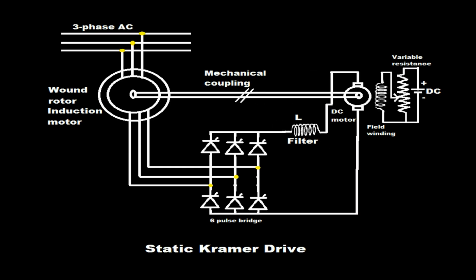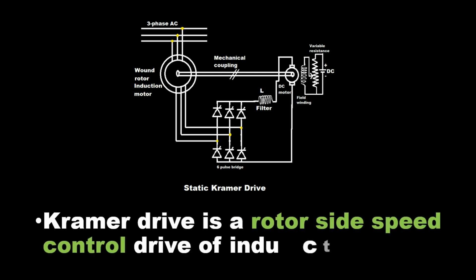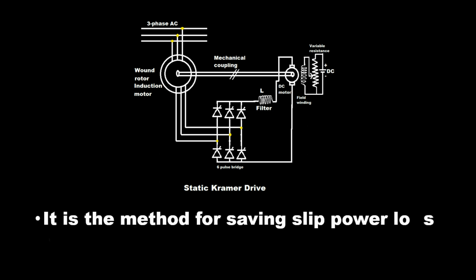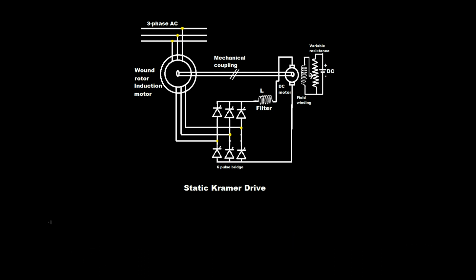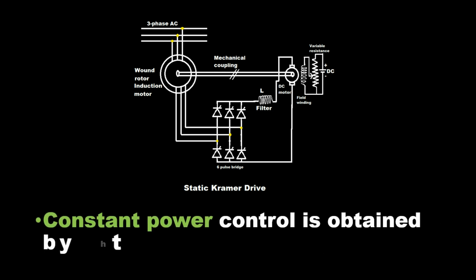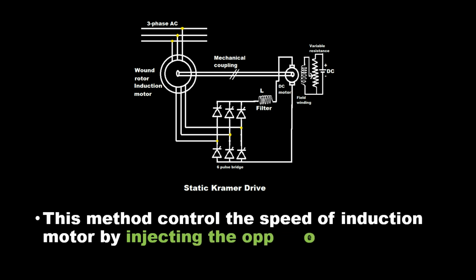The Static Kramer Drive is a rotor side speed control drive of an induction motor. Slip is the difference between synchronous speed and rotor speed. It is a method for saving slip power loss in the rotor by returning power back to the line. It converts the slip power into AC power and returns it back to the line. Constant power control is obtained by this method.